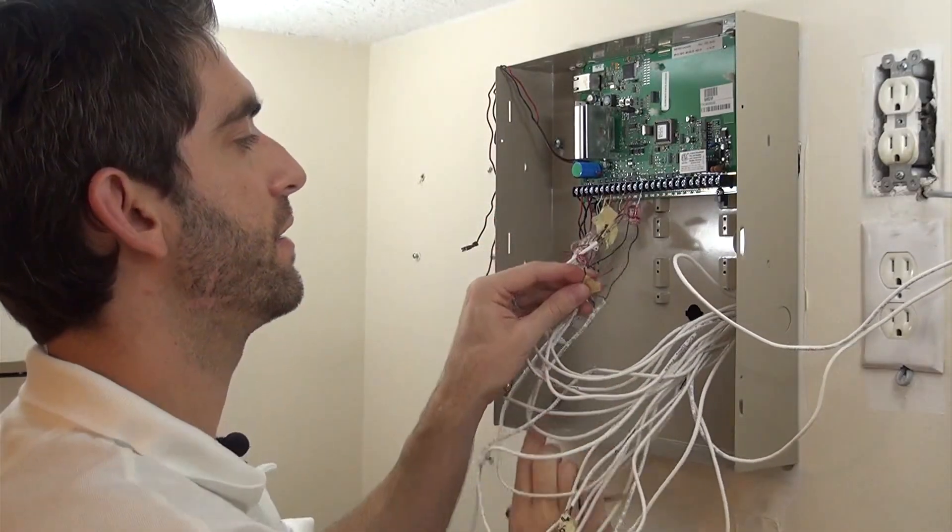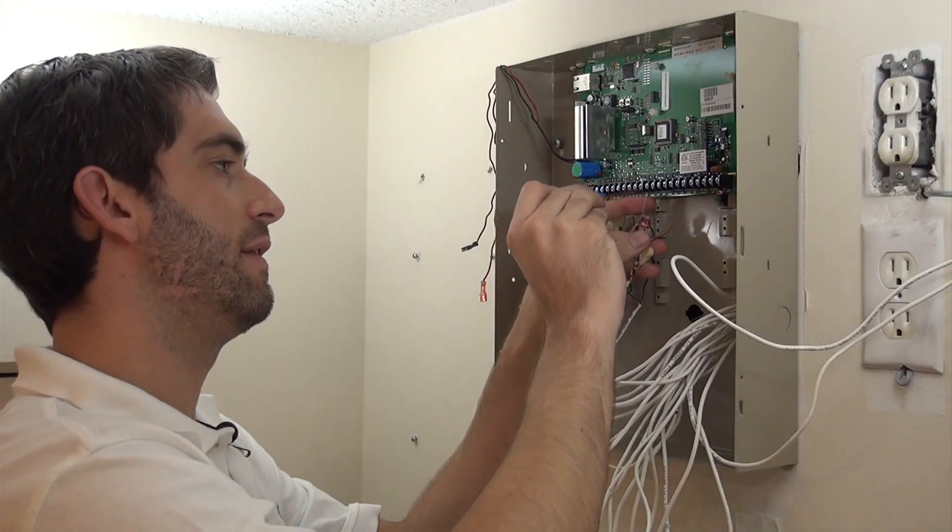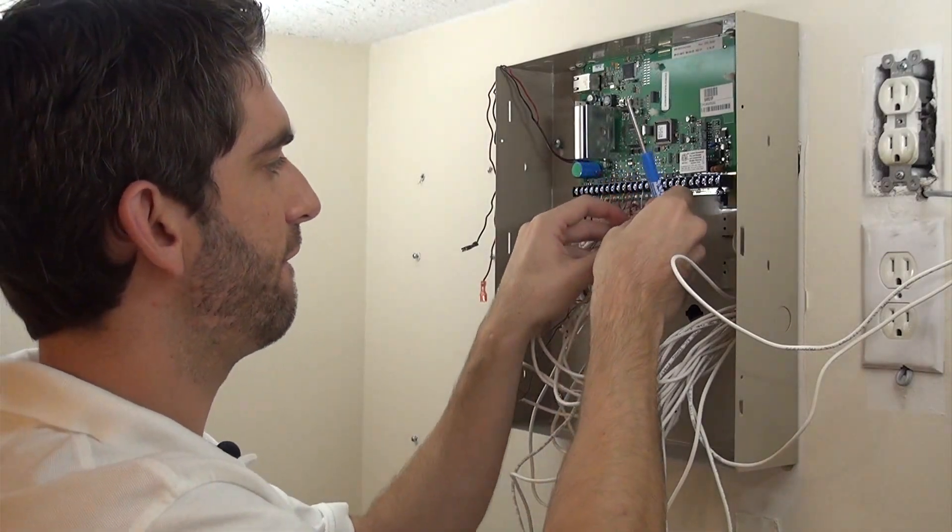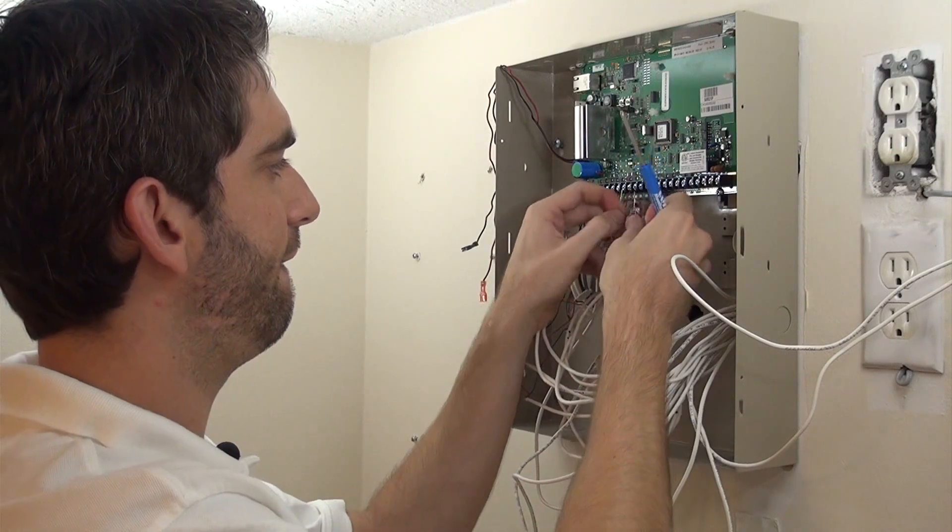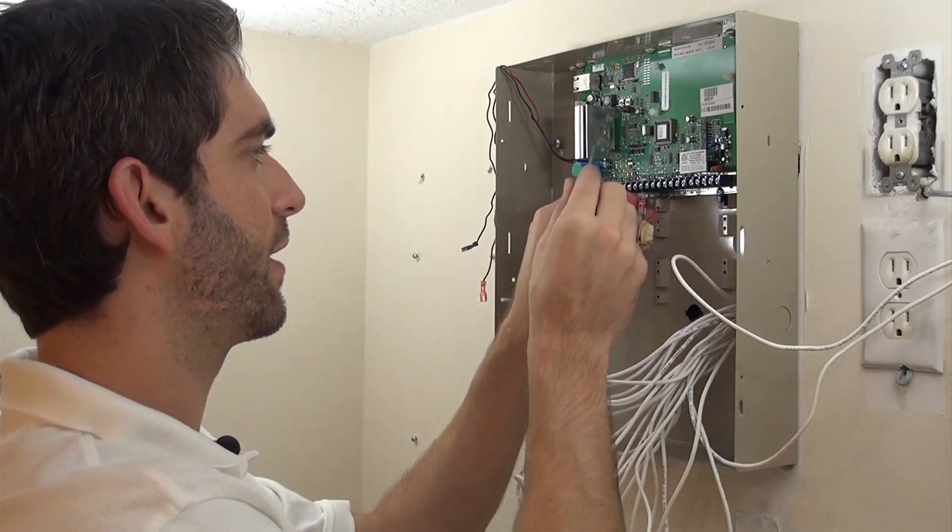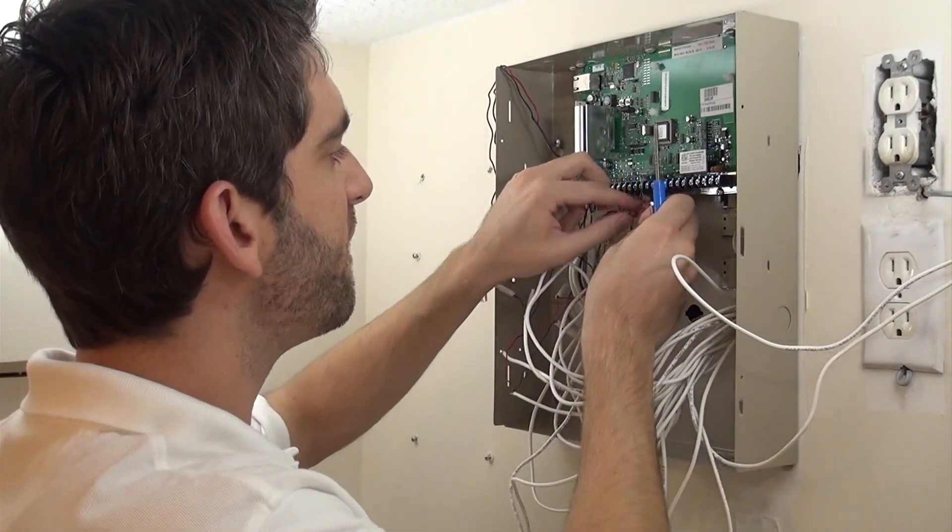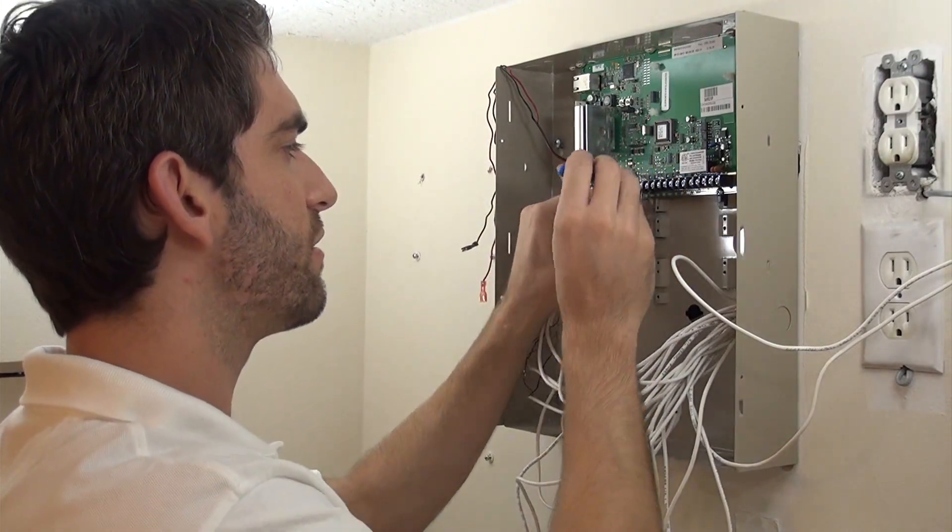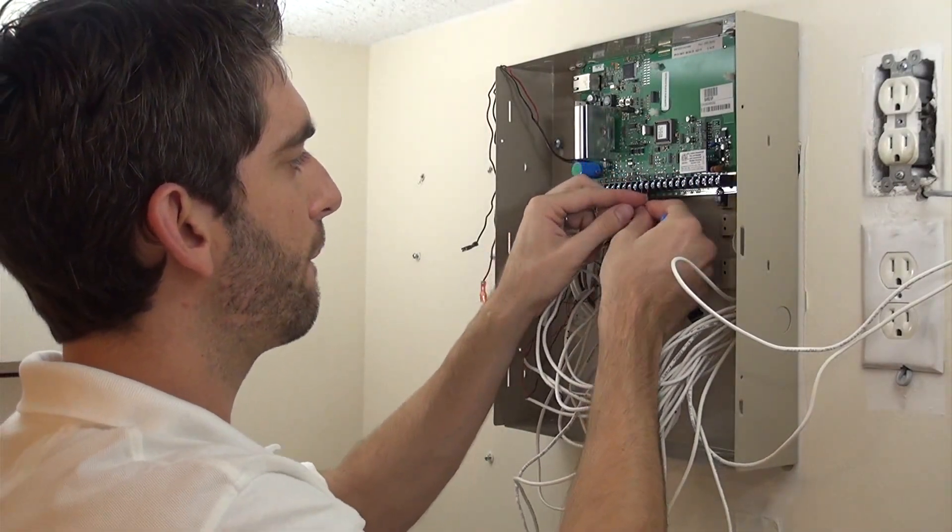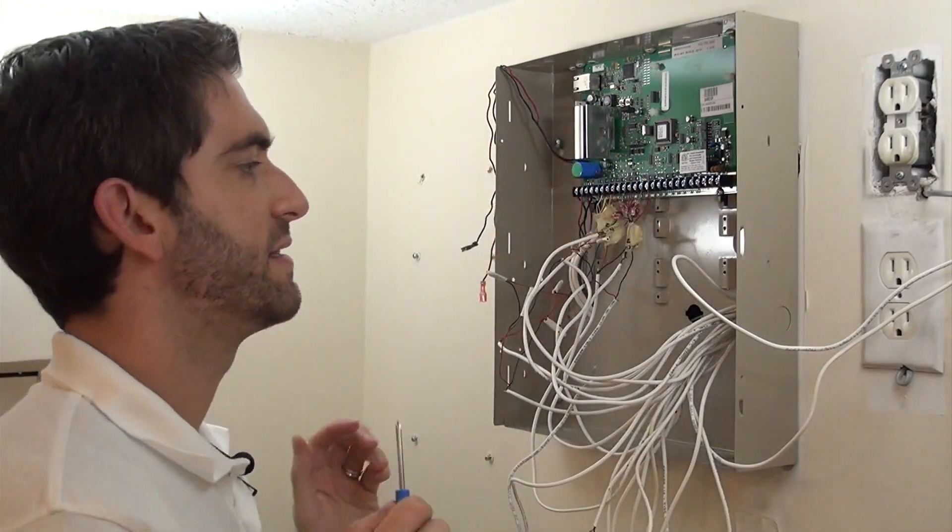And we're going to land this to zone 4. Feed it up and under, and since zone 4 is a shared common with zone 3, we're going to use the same terminal that we have zone 3 connected on. Feed the wire up and in. There we go, we've got both our commons for zone 3 and zone 4. And then we're landing zone 4 to the screw terminal labeled Z4. Nice and tight, good to go.